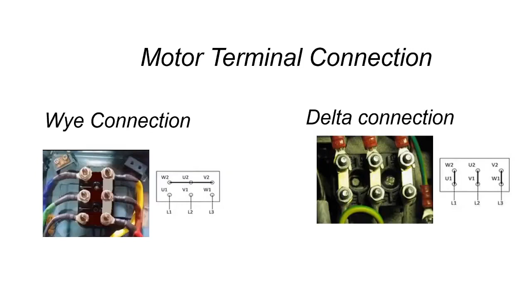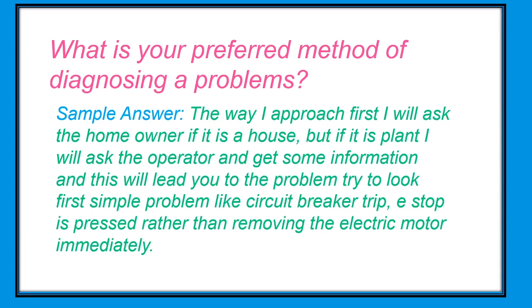What is your preferred method of diagnosing a problem? Sample answer: the way I approach it first, I will ask the homeowner if it's a house, but if it's a plant, I will ask the operator and get some information, and this will lead you to the problem. Try to look first at the simple problem, like a circuit breaker trip or e-stop being pressed, rather than removing the electric motor immediately.